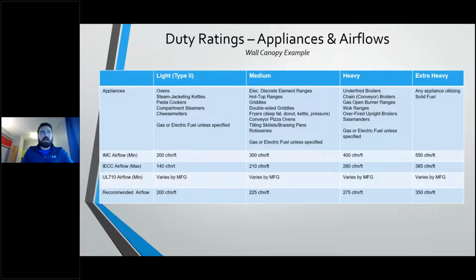Now, the other types, so your standard appliances, would be heavy or medium. So what determines if this is going to be heavy or medium? It's going to be the worst case scenario of the cooking appliances underneath the hood. So let's say our appliance lineup is one oven, one griddle, one fryer, and a gas charbroiler. That gas charbroiler is going to be my heavy application. So now I have to design this entire hood under a heavy classification. So what does that mean? That heavy classification is going to be designated by IMC 400 CFM.